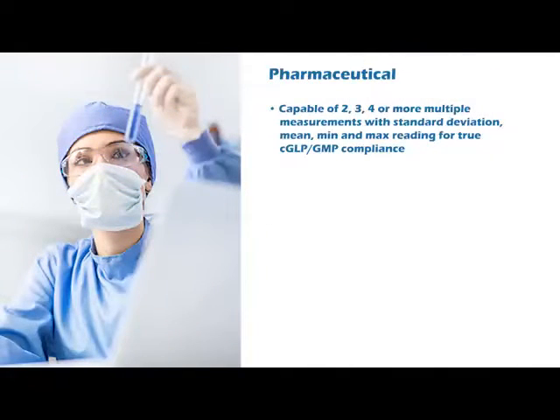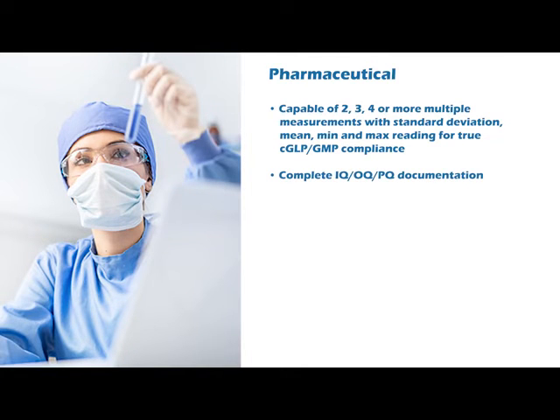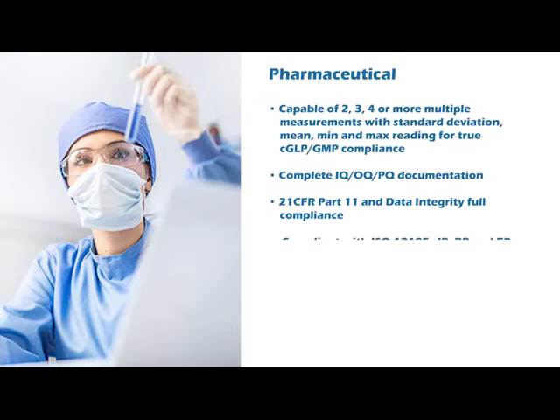For pharmaceutical applications, the meter is capable of 2, 3, 4, or more multiple measurements with standard deviation, mean, min, and max reading for true cGLP-GMP compliance. Complete IQ, OQ, and PQ documentation is provided. Full compliance with 21 CFR Part 11 and data integrity is included, along with compliance to ISO 12185, JP, BP, and EP.